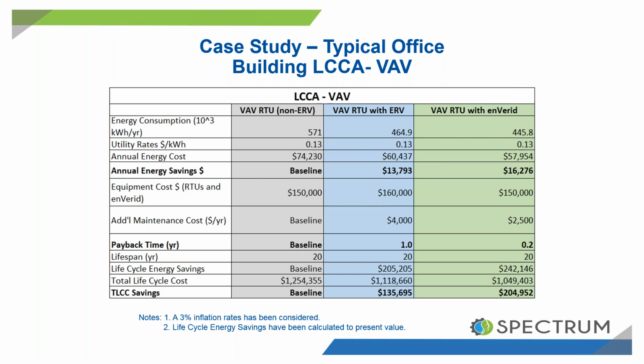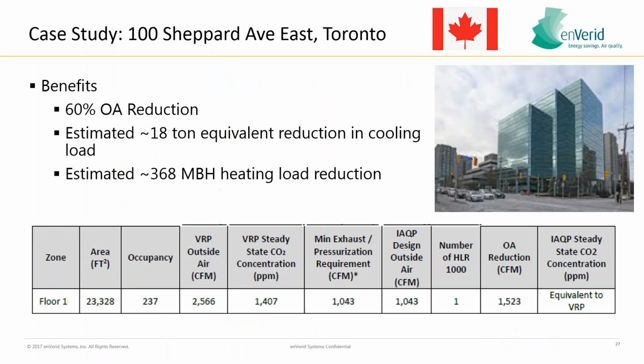All these dollar amounts are US dollars, but you can see that the equipment costs of these three systems are all pretty much the same. EnVerid's a little bit cheaper than with energy recovery. The maintenance costs are actually fairly reasonable and indeed potentially less than energy recovery. And the life cycle cost analysis shows almost doubling the amount of savings versus energy recovery, because reducing outside air is so much more efficient than using energy recovery on that same air. That's just a sample there.